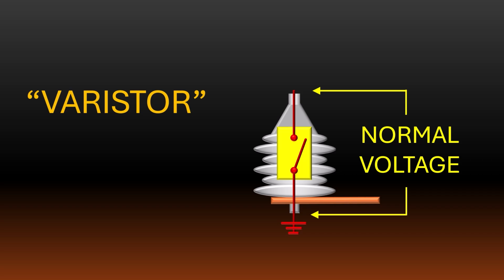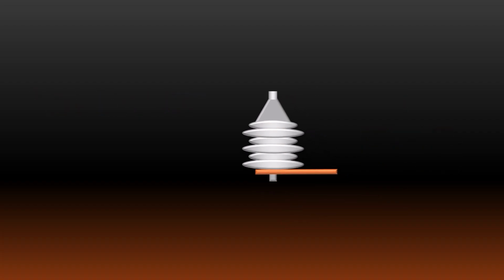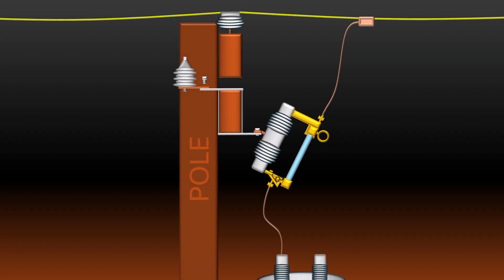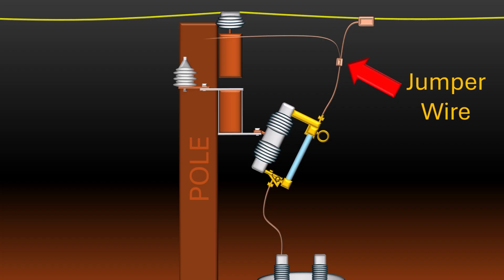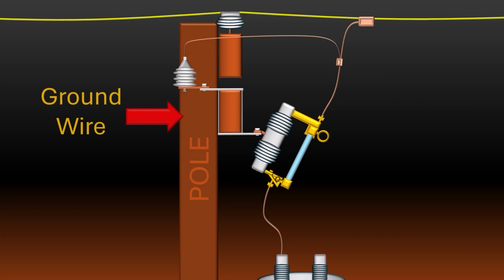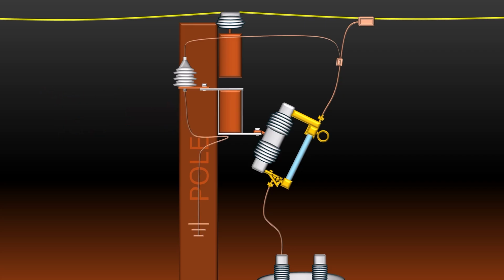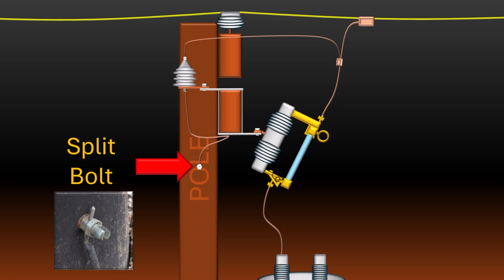In areas where lightning strikes are known to occur, these get installed on the other side of the same crossarm mounting bracket used to attach the cutout. It's connected by using a crimp connector and a short jumper wire, usually attached to the same lead wire attached to the cutout. A ground wire is attached to the bottom of the arrestor and attached to the underside of the crossarm and down the pole to a ground rod. If this is a steel pole, the ground wire will be attached to the steel pole near the crossarm with a split bolt.